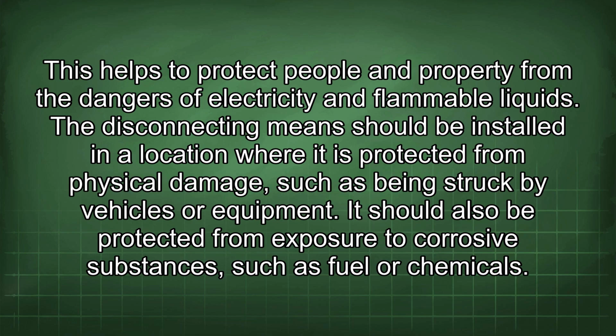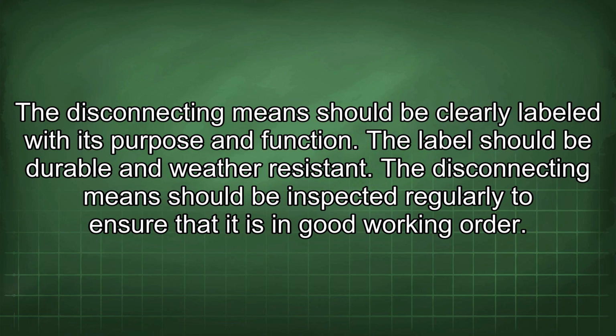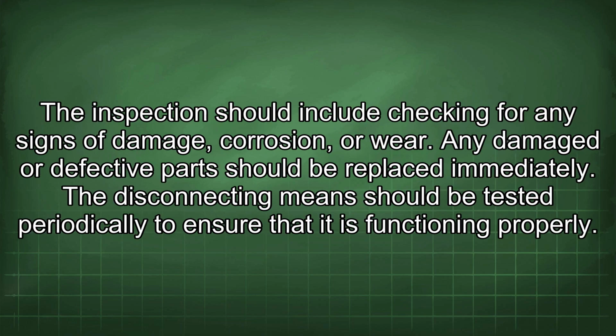The disconnecting means should be installed in a location where it is protected from physical damage, such as being struck by vehicles or equipment. It should also be protected from exposure to corrosive substances, such as fuel or chemicals. The disconnecting means should be clearly labeled with its purpose and function. The label should be durable and weather resistant. The disconnecting means should be inspected regularly to ensure that it is in good working order. The inspection should include checking for any signs of damage, corrosion, or wear. Any damaged or defective parts should be replaced immediately.